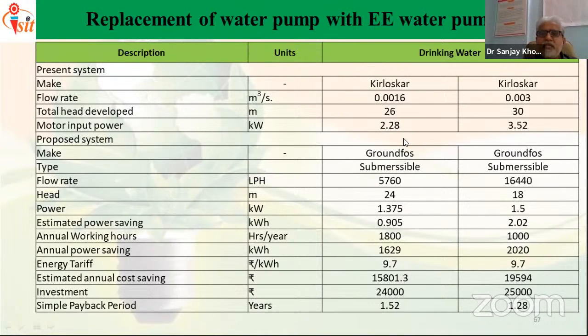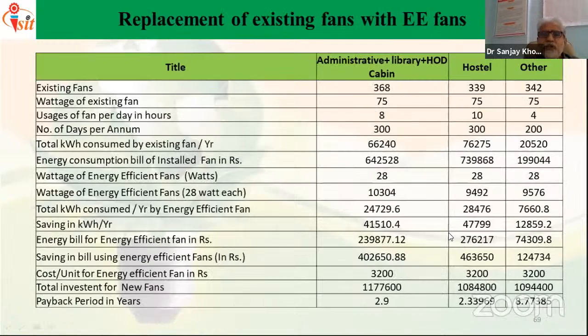Now we have recommended a Grundfos pump, submersible type. Flow rate is 5760. The head is the same. Now power consumption would be 1.375. Earlier it was 2.28. That means the estimated power saving would be around 1 electric unit, or 0.9 electric unit. Annual working hours we have taken as 1800. Annual power saving comes to 1629. Tariff is this. Estimated annual cost saving is 15,000. And investment for this energy efficient pump is 24,000. So payback is 1.5. Similarly, we can do it for the other pumps also.